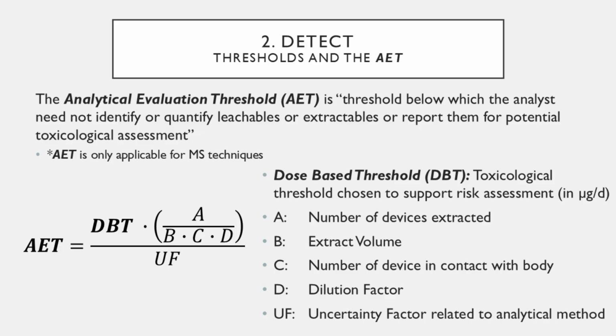Now, it's really only used for mass spectrometry methods. Methods like ICP, inductively coupled plasma mass spectrometry, are so sensitive, as generally acknowledged, that they're going to be able to detect things at incredibly low concentrations. So there's really not a concern that you're meeting a minimum. It's for other instruments that are more susceptible to this type of issue, which is why it only comes in the space of those organic compounds that look at gas chromatography or liquid chromatography coupled with mass spec.